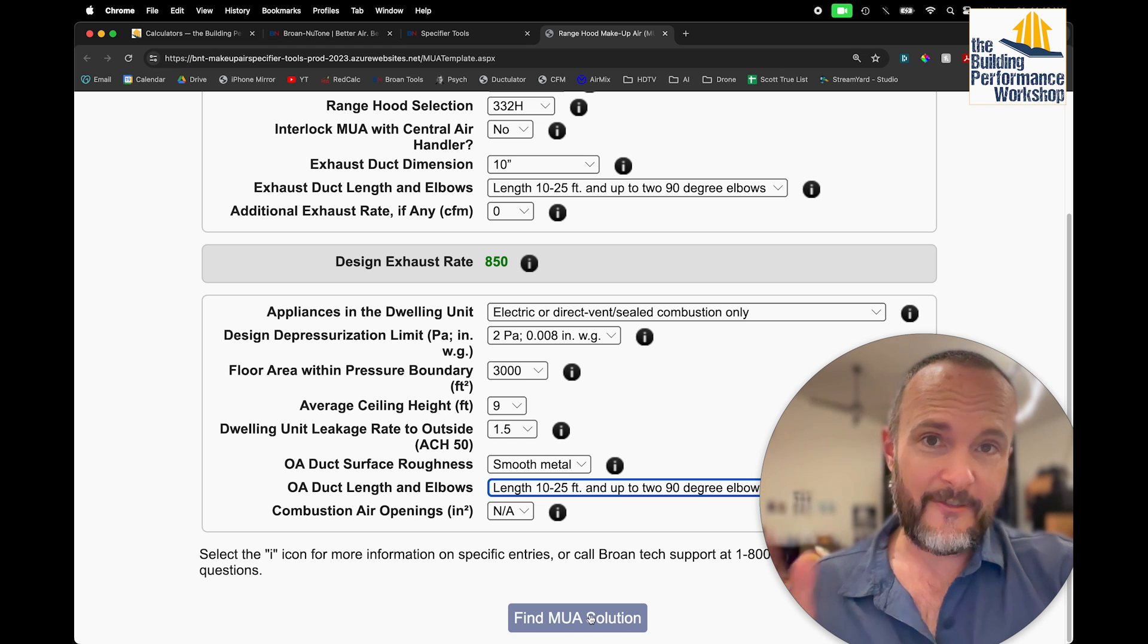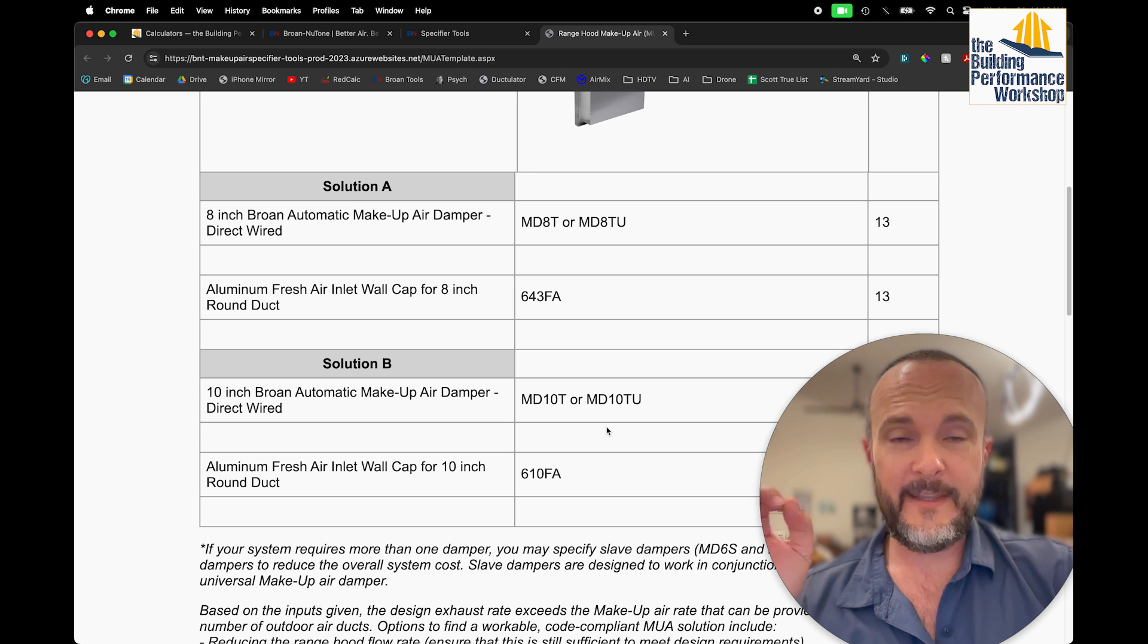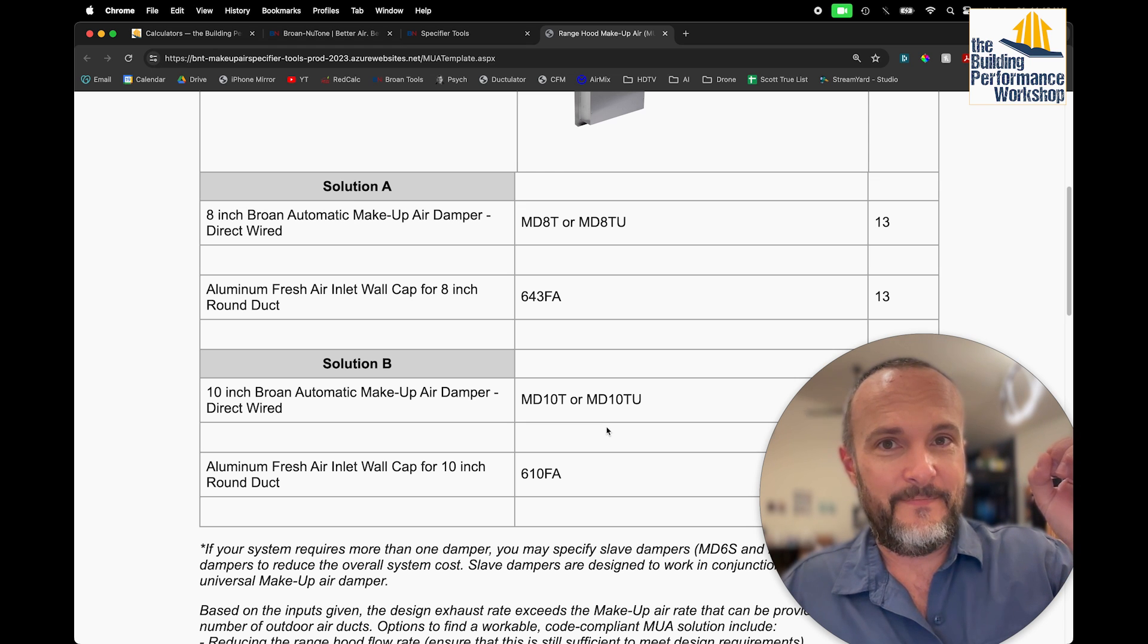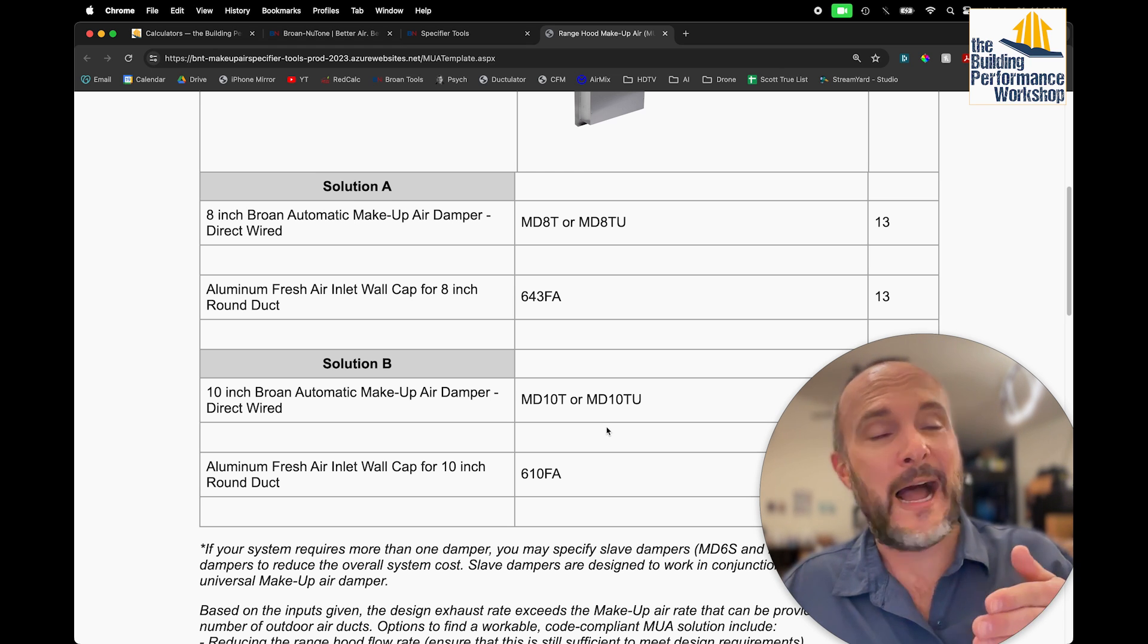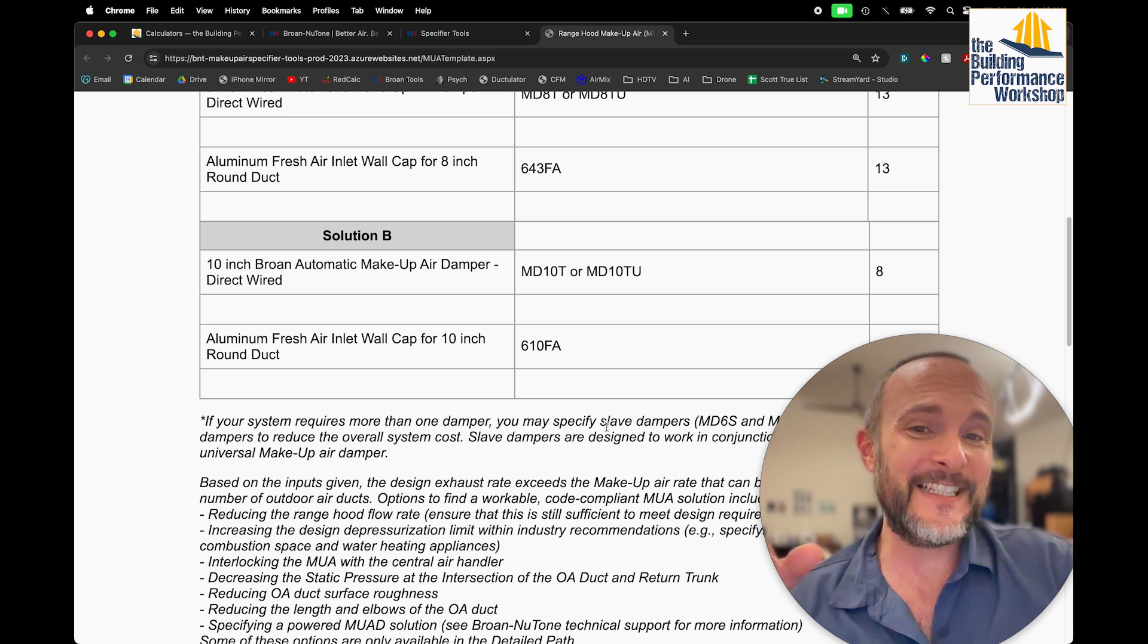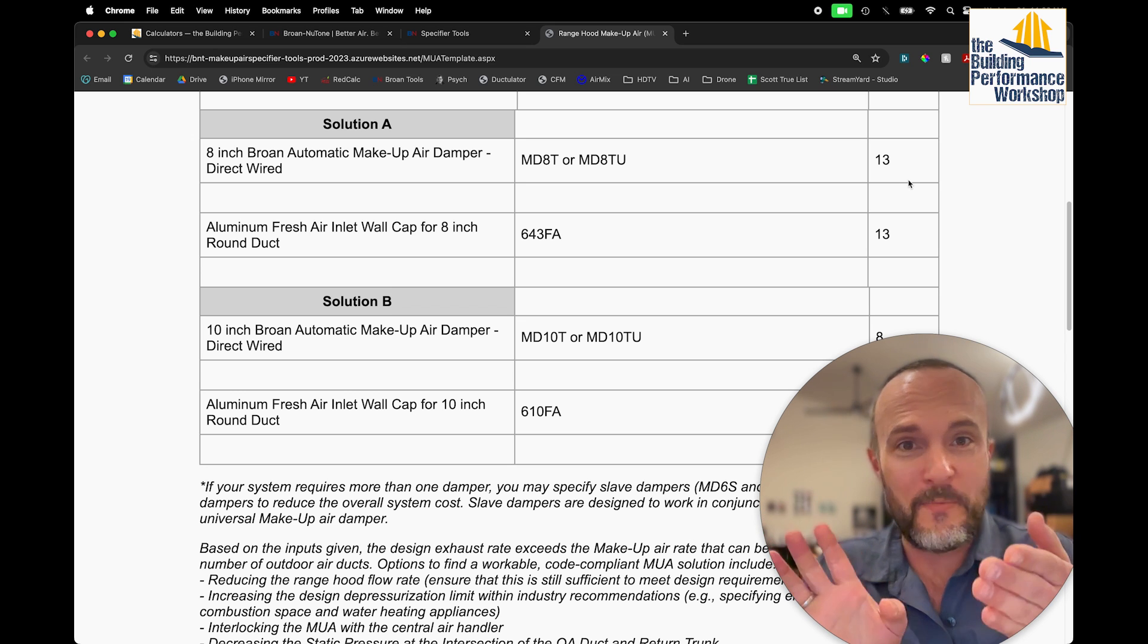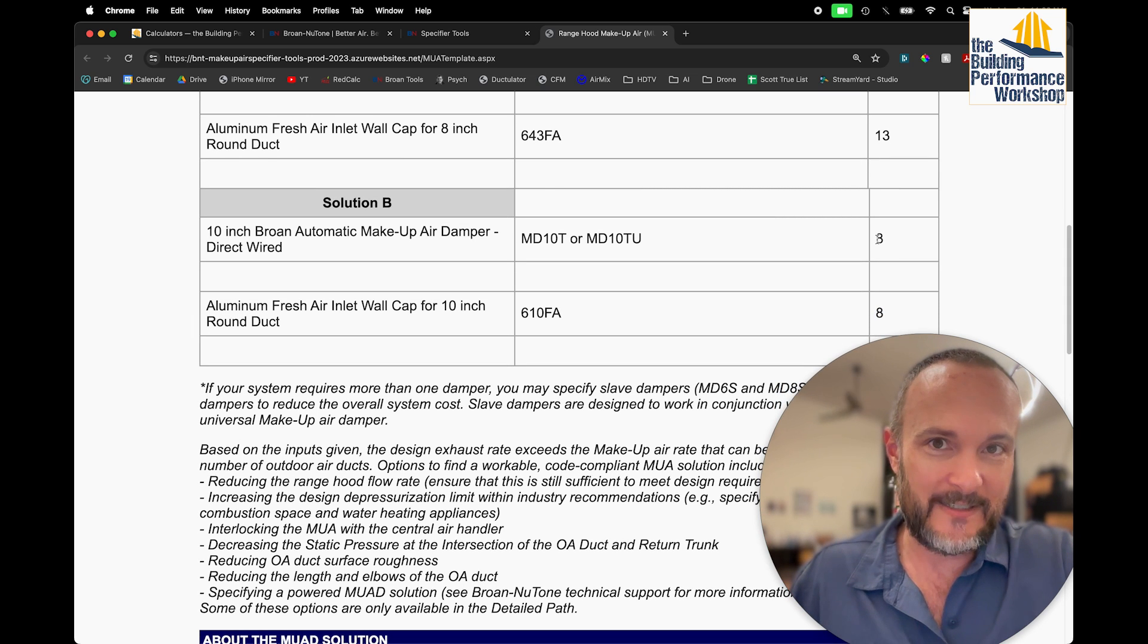Now I'm going to click Find MUA Solution, and it's going to tell me that I need 13 8-inch round ducts. Before, I was aiming at 0 ACH-50, and now I'm aiming at 1.5. Before, I had a 900 CFM fan. Now I actually have only 760 because of the ducting that I attach to it. And so now this calculator is actually working, and it's actually telling me real-life 13 8-inch holes to outside that all dampers open up at the same time when I kick on my exhaust hood. Or you could do it with 8 10-inch ducts.